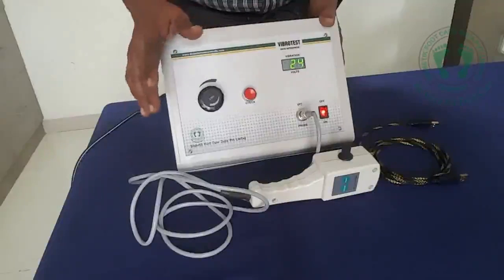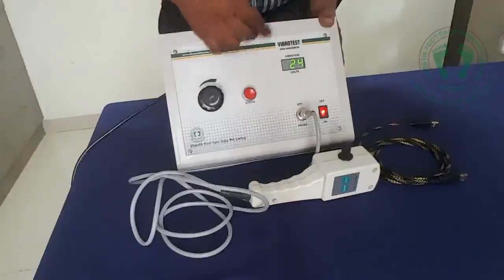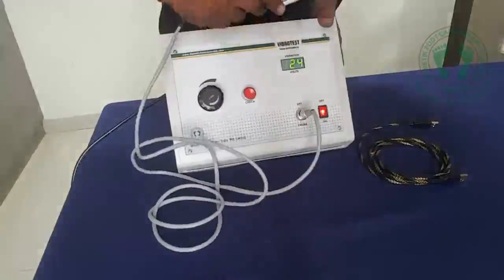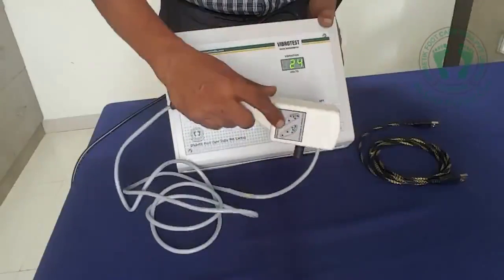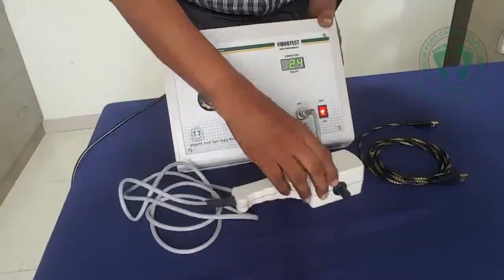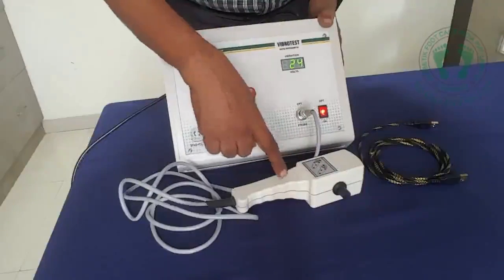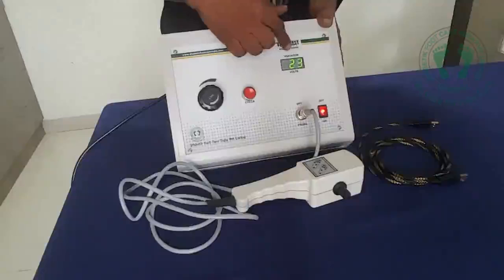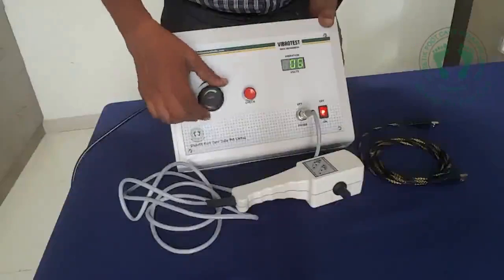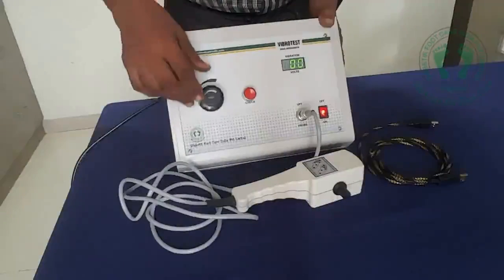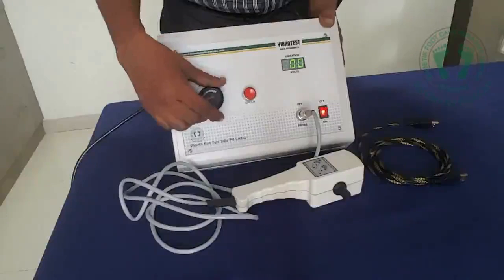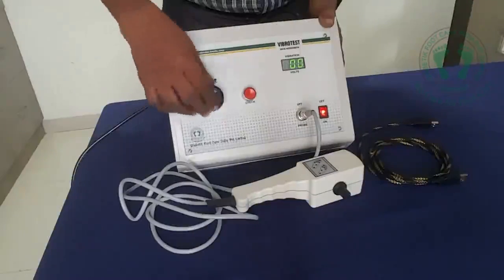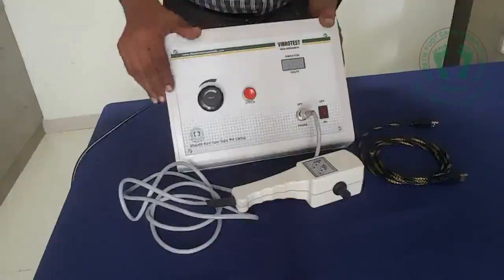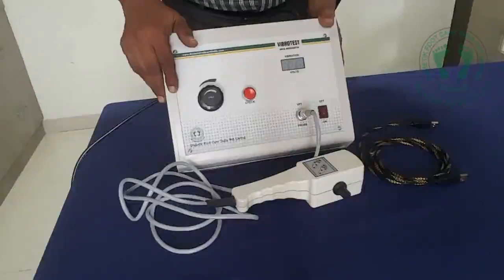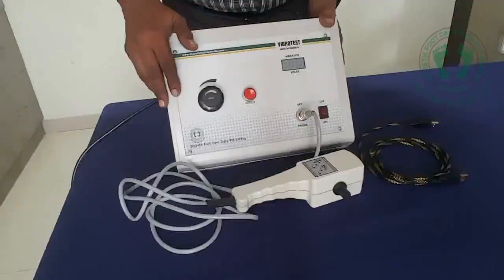So this is the procedure. We need to test at multiple points; the locations are given, 6 points per foot. Once you complete all the testing, we have to bring it back to 0, counterclockwise, and then switch off the device. Always make it a point to bring it to 0 this way, so the life of the machine will last longer.